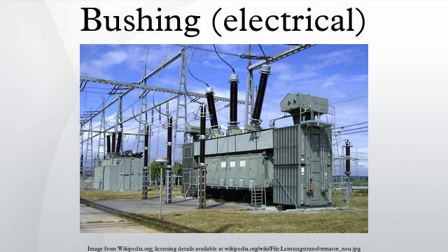When an energized conductor is near any material at earth potential, it can cause very high field strengths to be formed. Bushing condenser: a bushing must be designed to withstand the electrical field strength produced in the insulation, when any earth material is present. As the strength of the electrical field increases, leakage paths may develop within the insulation. If the energy of the leakage path overcomes the dielectric strength of the insulation, it may puncture the insulation and allow the electrical energy to conduct to the nearest earthed material, causing burning and arcing.